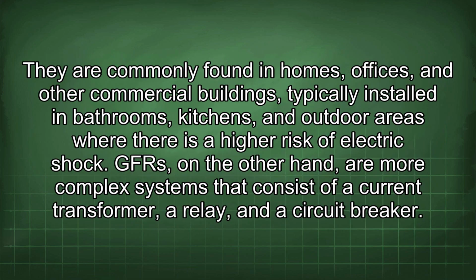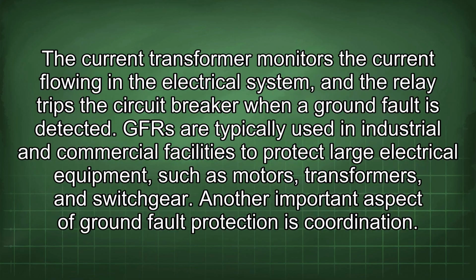They are commonly found in homes, offices, and other commercial buildings, typically installed in bathrooms, kitchens, and outdoor areas where there is a higher risk of electric shock. GFRs, on the other hand, are more complex systems that consist of a current transformer, a relay, and a circuit breaker. The current transformer monitors the current flowing in the electrical system, and the relay trips the circuit breaker when a ground fault is detected. GFRs are typically used in industrial and commercial facilities to protect large electrical equipment such as motors, transformers, and switchgear.